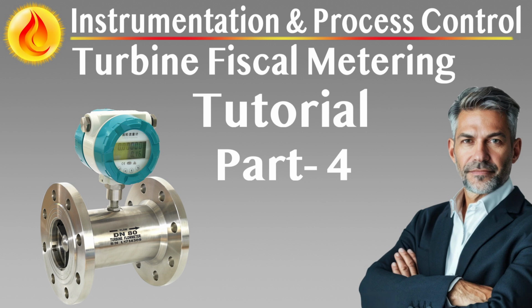Calibration facilities and support equipment. When specified, the manufacturer must provide a complete suite of calibration tools and verification standards for field use. This may include temperature baths for RTD verification, deadweight testers for pressure transmitter calibration, reference fluids for densitometer checks, known water cut blends for inline meter validation, portable communicators for digital transmitter interrogation.